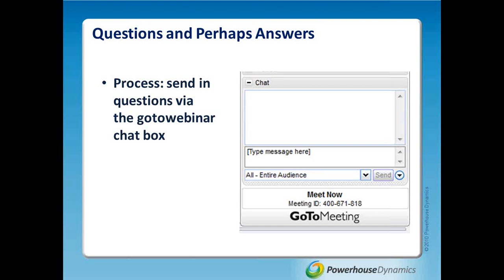Well, it's a great question, it comes up pretty frequently. I'd say it depends on the hours you can raise that set point. For a quick serve restaurant running 16, 18 hours a day and shutting down from 2 o'clock to 7 or 8 in the morning if they don't have a breakfast crowd, if you're able to harness a 4 to 6 hour window and let your set point drift from 74 degrees up to the low 80s, I would say do that. We've done the math, and it works to the advantage of our clients to raise that set point, then come back in the morning and cool down 8 to 10 degrees.